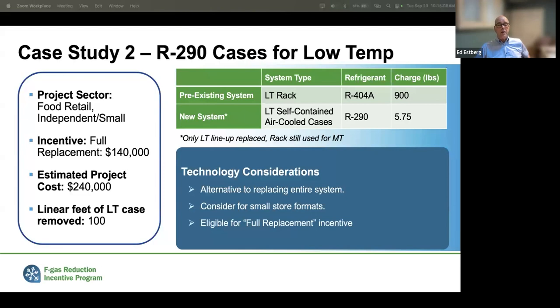This project, we estimate, is going to cost about $240,000. You get over half of that in the incentive because the new cases actually have a condensing unit in them, so we're treating this as a full replacement. This was only 100 feet of case. So if you're a retailer and you want to change just your low temp and you're on a central system, you can put in R290 self-contained cases and just discontinue use of the low temp on the existing rack and still get the full incentive. It's good for small format stores, and again, it's a full replacement incentive. Next slide, please.